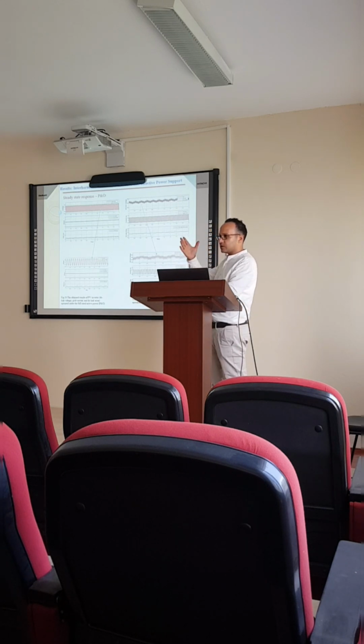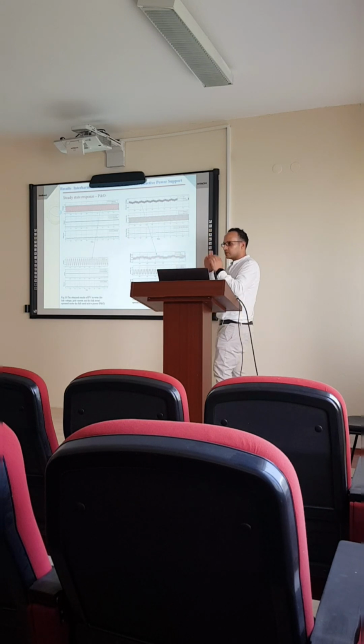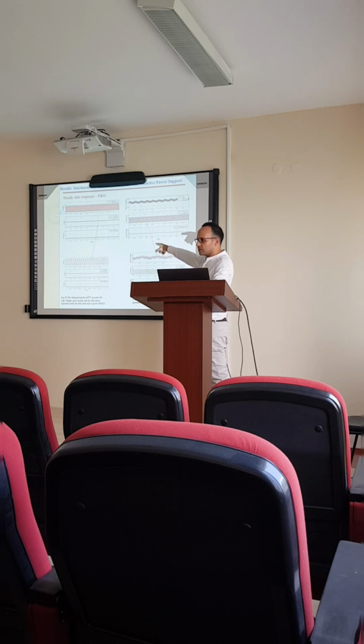It's only that I got all the results in a single slide after that. But this is the status information. I wanted to show the phase shift because this controller is working with active power support, so one should see the phase. It's in phase, and also the perturbation of the DC link along with the value of the grid. By the way, all the designs comply with the grid standards. The total harmonic distortion in this figure is very low, so it complies with the grid connection standard.